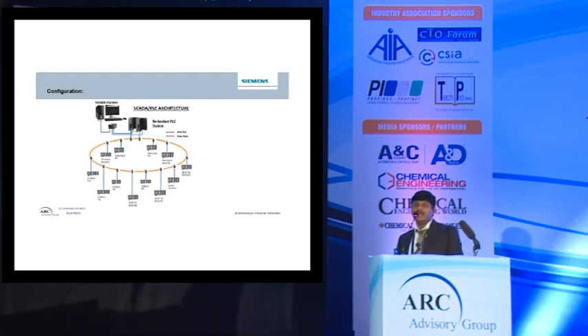The MLCP didn't have an automation system. They had only a manual system where jet fans were controlled just by switching on manually - by knowing the CO2 level and CO level, they would go and switch on the jet fans manually, and the ventilation system would run. That's where they were losing lots of energy.